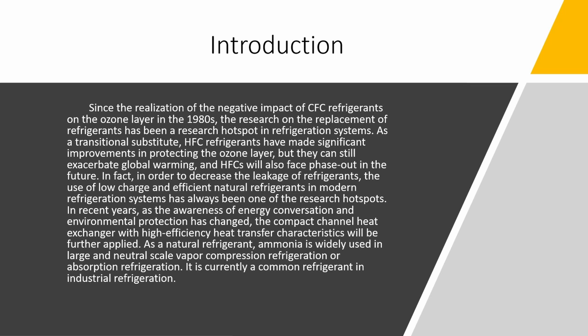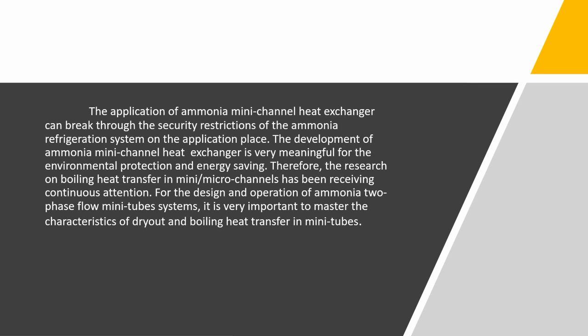As a natural refrigerant, ammonia is widely used in large-scale vapor compression refrigeration or absorption refrigeration. It is currently the most commonly used refrigerant in industrial refrigeration. The application of ammonia mini-channel heat exchanger can break through the security restrictions of the ammonia refrigeration system on the application place. The development of ammonia mini-channel heat exchanger is very meaningful for environmental protection and energy saving.